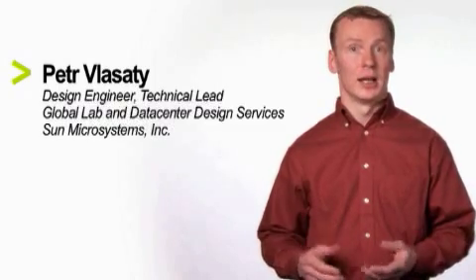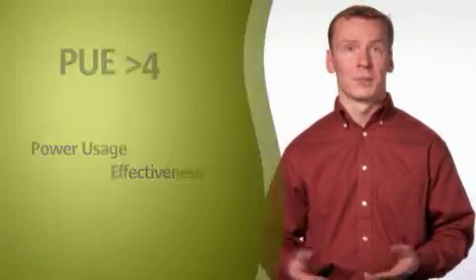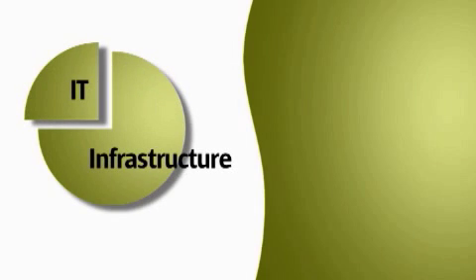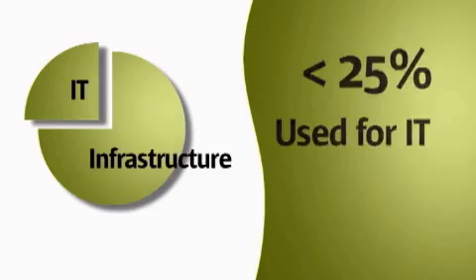The Louisville data centers were built over 10 years ago, when densities were not a concern, and the cost of inefficiency wasn't registering on the CFO's radar. We had numerous data center rooms that had a PUE of greater than 4. They were the worst in our portfolio. That means less than 25% of actual power was used to run the IT equipment.